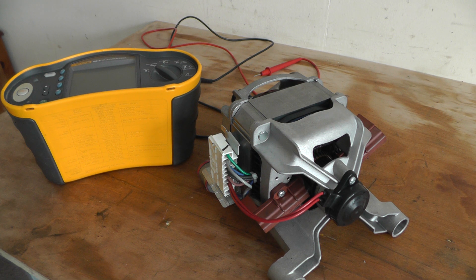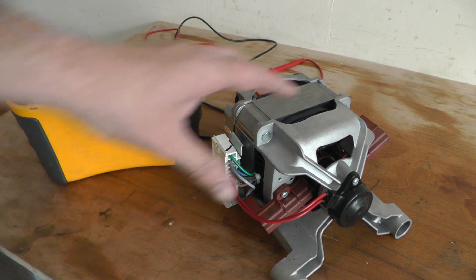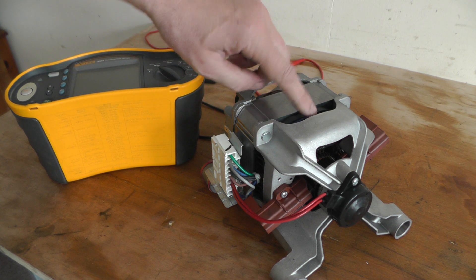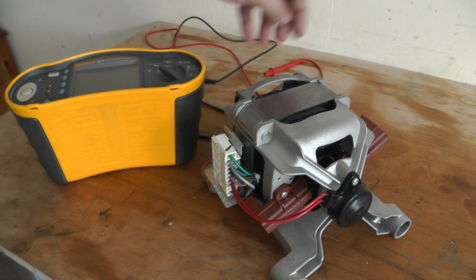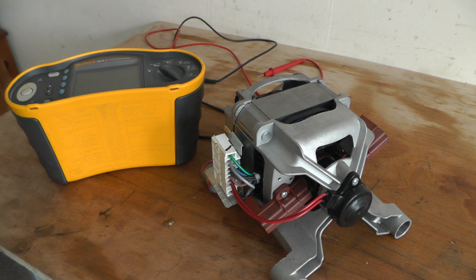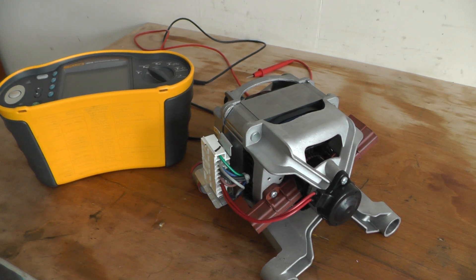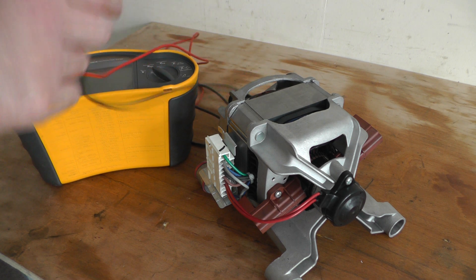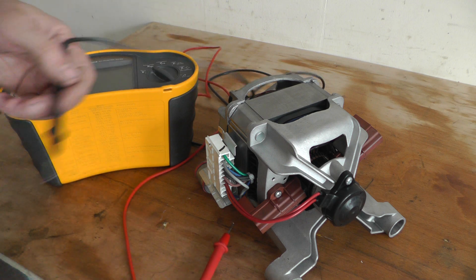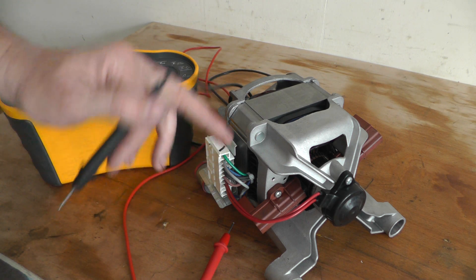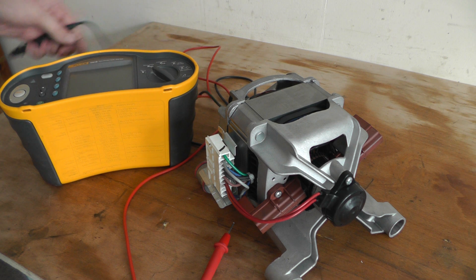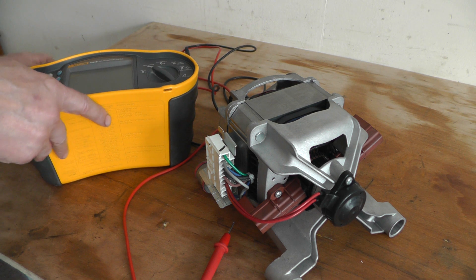Okay, so if your washing machine or any motor for that matter is tripping the electric, it could be because the insulation on the rotor or the windings is wearing down. So I'm just going to test at 250 and then at 500 volts the windings to earth. It should tell you if the insulation is okay. So I've got the leads in properly, I'll turn it on.